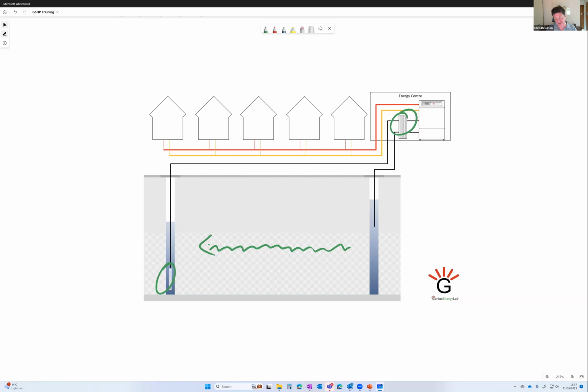There are also statutory licensing requirements in much of the world for this type of technology. In England at the minute, the licensing process for an open loop system is taking 12 to 16 months, so it's quite a significant endeavor. My rule of thumb is if you can do closed loop, technically and economically, then you should, because you avoid that long-term maintenance and exposure to licensing — you've got those benefits. However, open loop is a brilliant technology, particularly for compact sites or high heat loads, and so on. It can be your only option really. So it's very much worth considering, and we specify and install both.